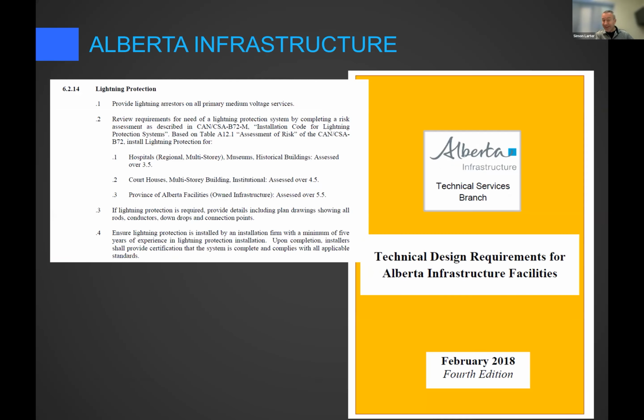Alberta Infrastructure also pays attention to lightning protection and requires a risk analysis. I know the fellow who maintains this design requirement document, and I think he's going to update it now to the new CSA B72 standard. The risk analysis in the old 1987 version wasn't particularly robust, so we reworked the entire risk analysis section. Now it harmonizes with 780, and it's more technical in nature, and doesn't give you those weird numbers like 3.5 or 4.5. Don't worry about that too much — that's on the engineering side, less on the inspection side.